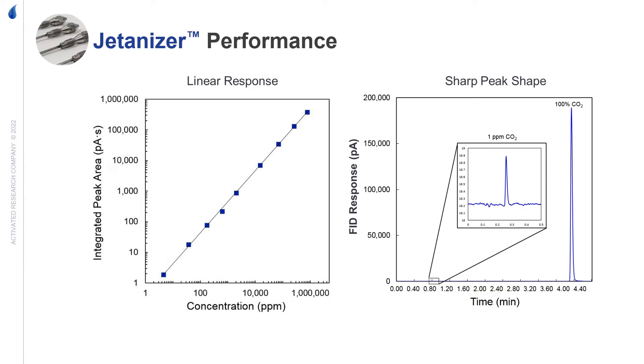Traditional nickel methanizers cannot handle high concentrations of CO2. ARC's patented catalyst has significantly higher activity relative to nickel. With the Jetanizer, there is a linear response from PPM levels to pure CO2 with sharp peaks.